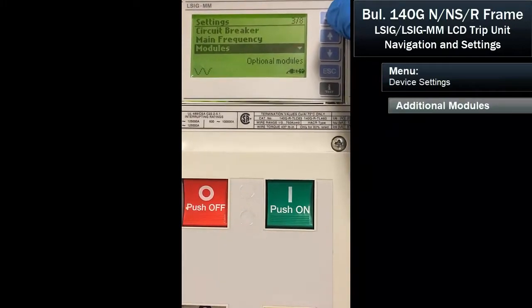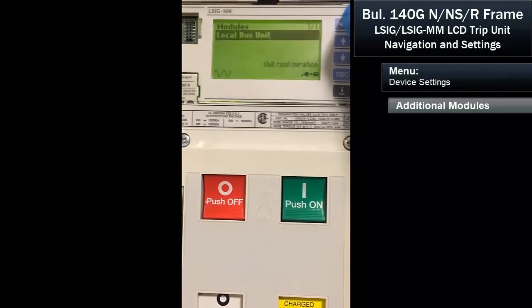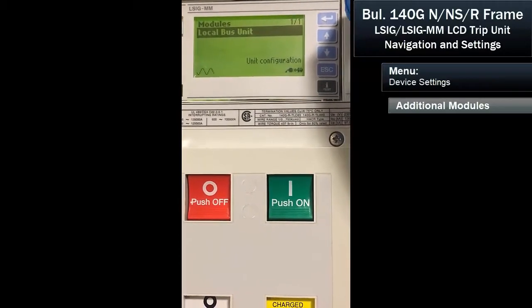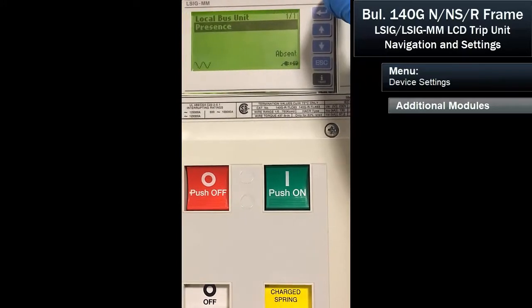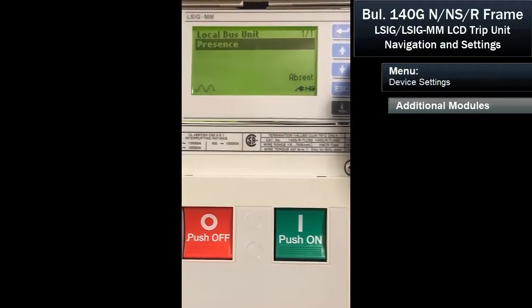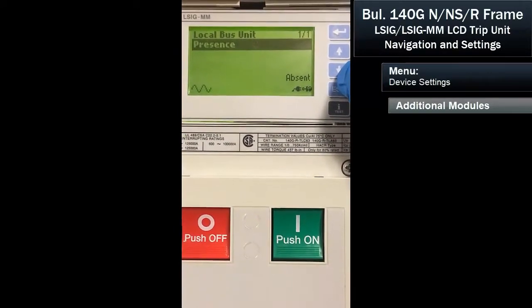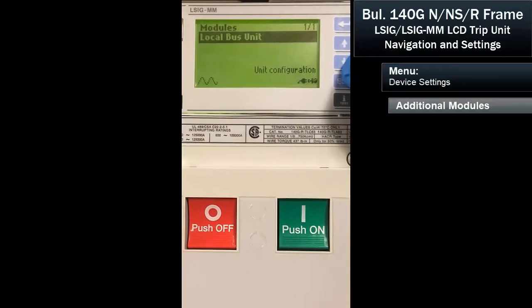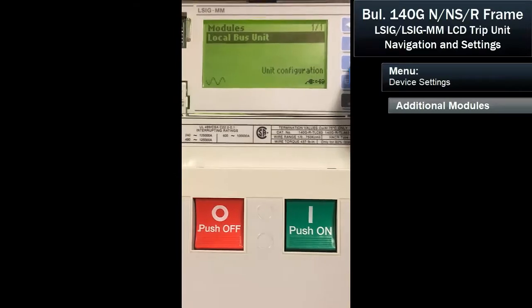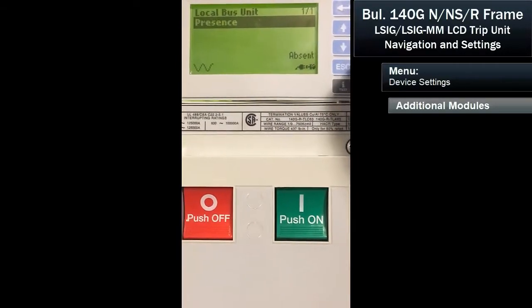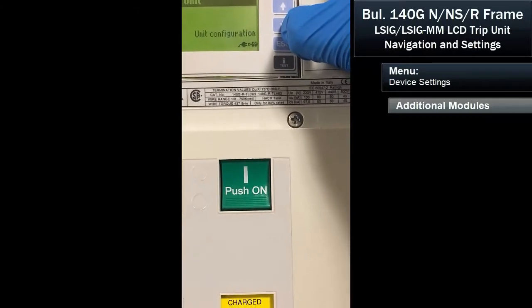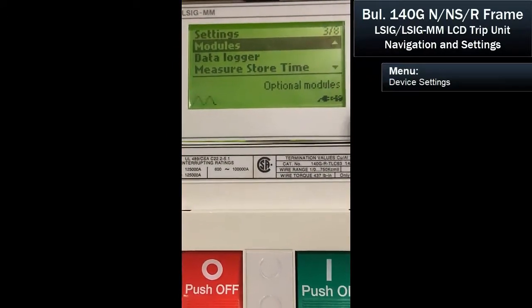If there are any additional modules installed in the breaker — this breaker has the ability to be installed on a communication bus. It's looking for a local bus unit, and when we hit enter, there's nothing installed in this particular breaker. So we can escape, and we're back at our settings menu.